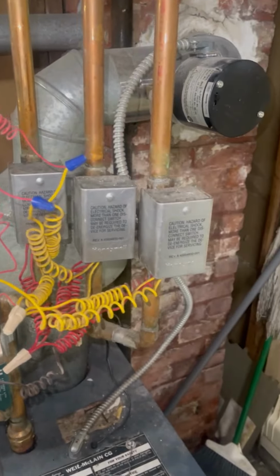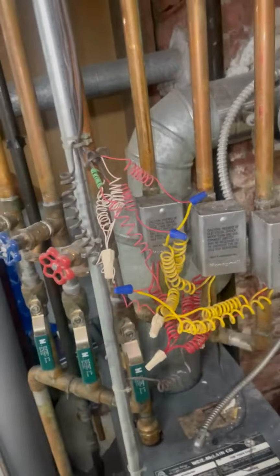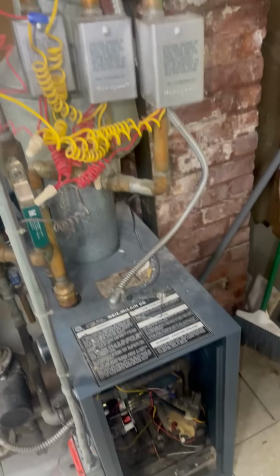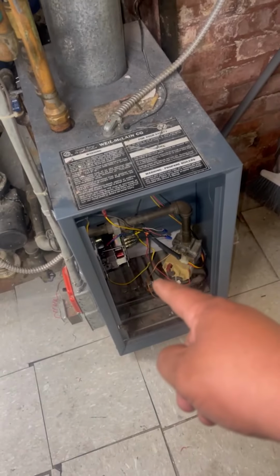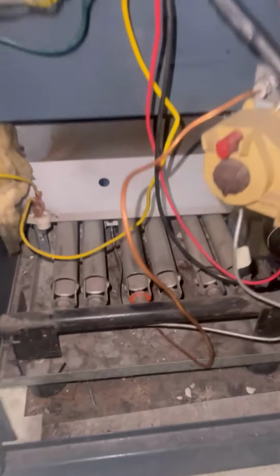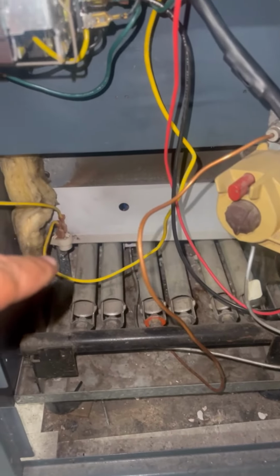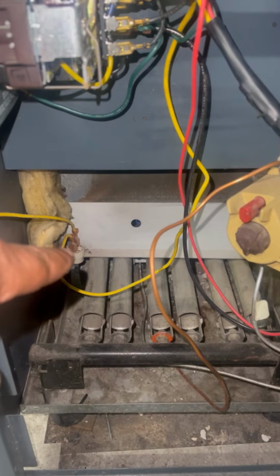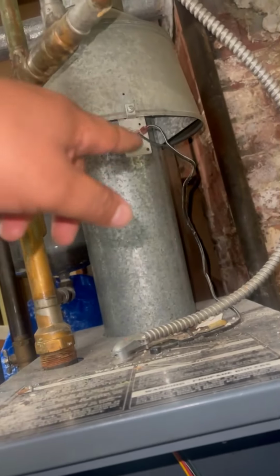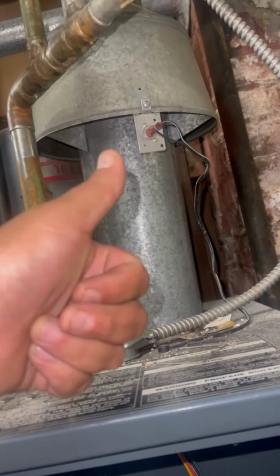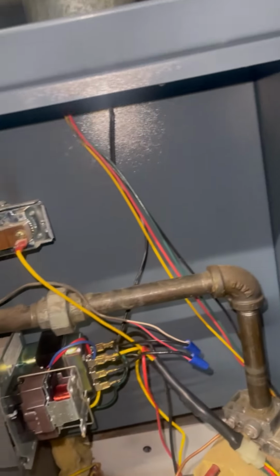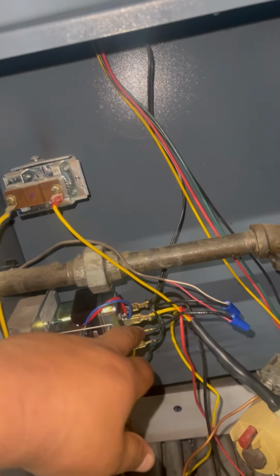So the call came in telling me that, yes, Louis, we're getting no heat. First thing I established, if there's a pilot on the bottom, there is a pilot there. It's kind of hard to see, but we have a pilot. Also, I double checked the rollout switch. If there's continuity, it's working. We also have continuity here on the spill switch. We're good to go. The next thing I also check is if there's power.